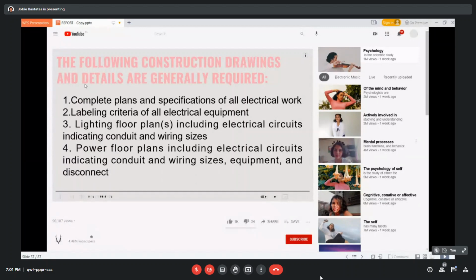Three, lighting floor plans, including electrical circuits, indicating conduit and wiring sizes. It deals with the actual number of lighting fixtures that a particular room will need. It is really important to indicate conduit and wiring sizes to ensure the reliability, consistency, and safety of the system. Fourth, power floor plans, including electrical circuits, indicating conduit and wiring sizes, equipment, and disconnect switches. It is a thorough planning tool because it gives an in-depth view of your building's electrical and wiring system.